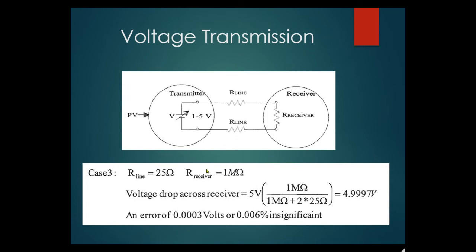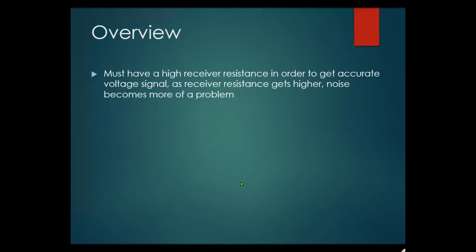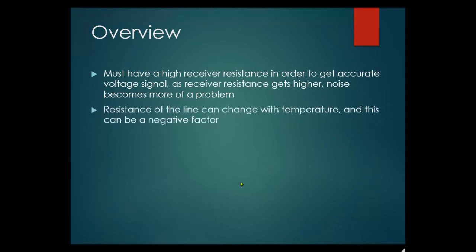Case three: with an even higher receiver resistance, the voltage drop approaches 4.9997 volts — an error of only 0.0003 volts, or 0.006%. This shows that for voltage transmission loops, you need a high-impedance receiver so most of the voltage drops across the receiver and not the lines. The receiver resistance must increase to achieve an accurate voltage signal, but as receiver resistance gets higher, noise becomes more of a problem and resistance of the line can change with temperature.